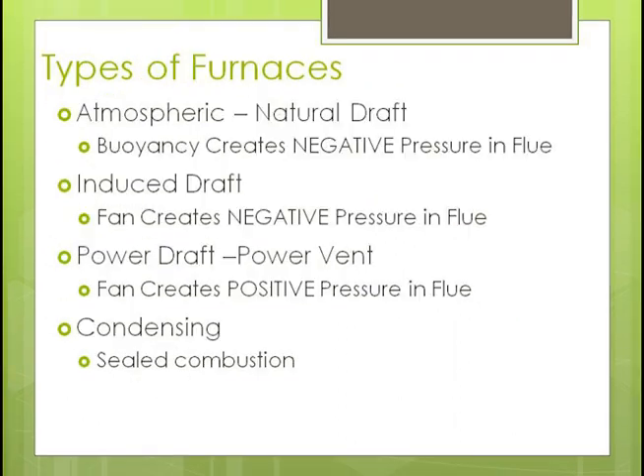We talked about the different kinds of furnaces. There are atmospheric or natural draft furnaces in the 60% to 70% efficient category. There are induced draft furnaces in the 80% category — make a note that an 80% furnace is the only one that has an induced draft, meaning the draft is pulled rather than relying on atmospheric venting. It has a little fan in it.